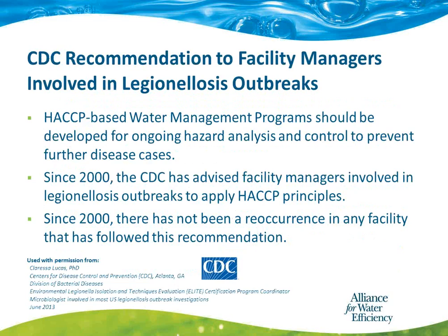So what I'd like to do now for just the next few minutes is talk to you about how to solve this problem. The good news is we can prevent these cases. The Centers for Disease Control and Prevention recommends to all facility managers in Legionellosis outbreaks that they should develop HACCP-based water management programs for ongoing hazard analysis and control to prevent further disease cases. Since 2000, the CDC has advised facility managers involved in Legionellosis outbreaks to apply HACCP principles to the management of their building water systems. And since 2000, there's not been a reoccurrence in any facility that has followed this recommendation.